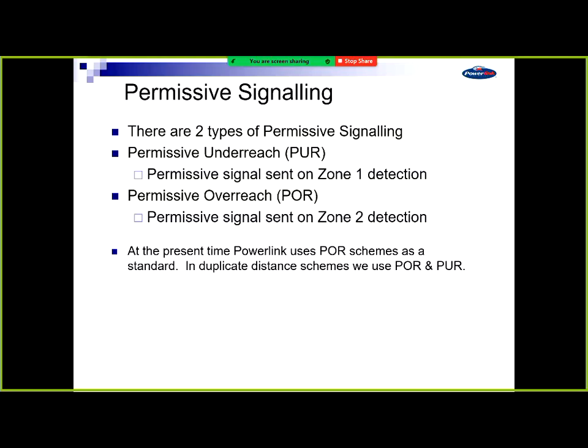One simple way to think of permissive overreach, or permissive signalling, is, there's a fault down the line, you're the relay at the remote end of the feeder, I'm the relay at this end of the feeder. I tell you the fault's in front of me, you tell me the fault's in front of you. It's got to be between us. It can't be anything else. So that's the way it works. You tell me that and it's right in front of me, but my zone 1 is already tripped. I say, oh, thank you, I know that, I've already tripped. And it's in your zone 2, you go, oh, you told me it's in front of you, it's in my zone 2, I'm going to go. It's not in my zone 1. If it's in both relays' zone 1, this signalling does nothing, because we've tripped instantaneously on zone 1 from both ends.